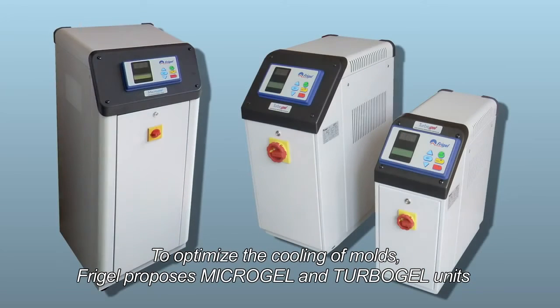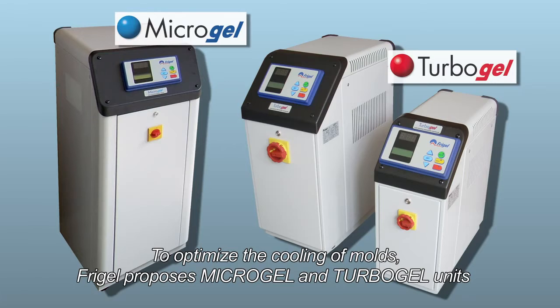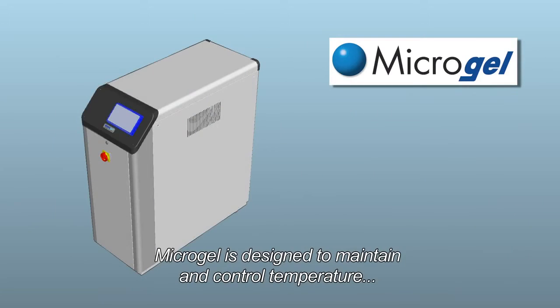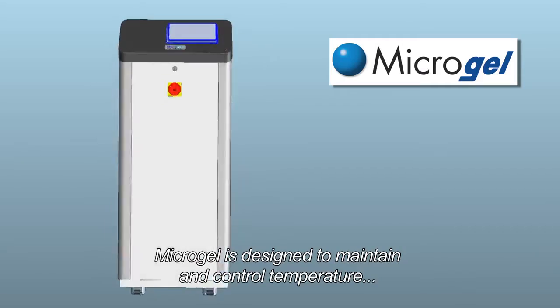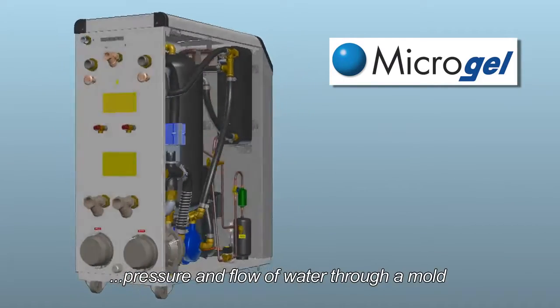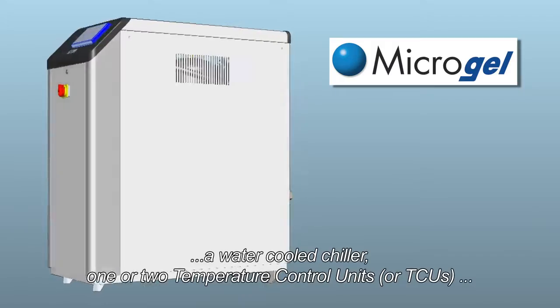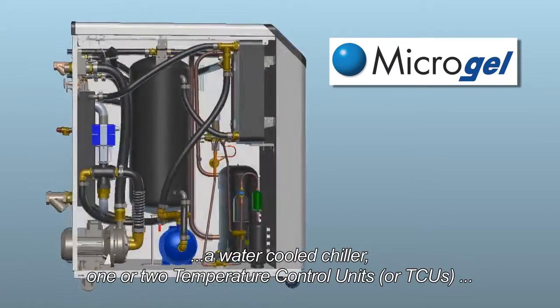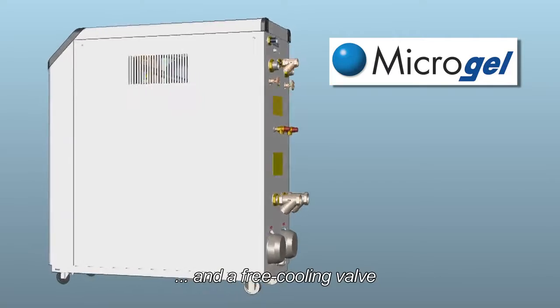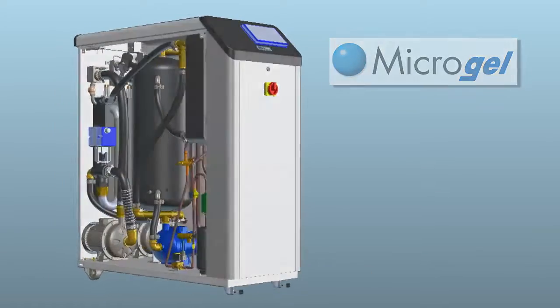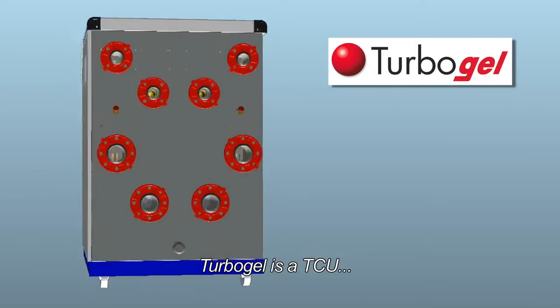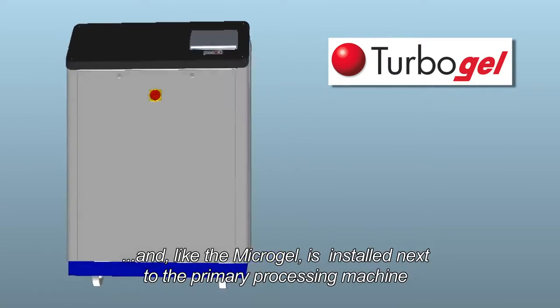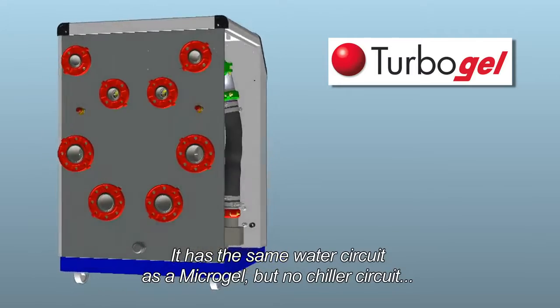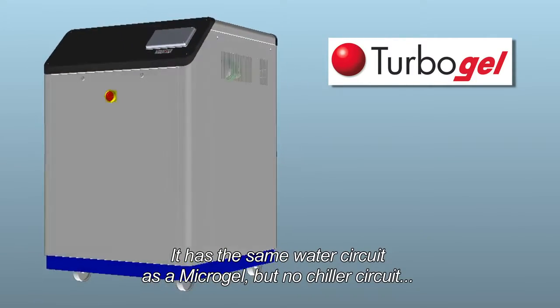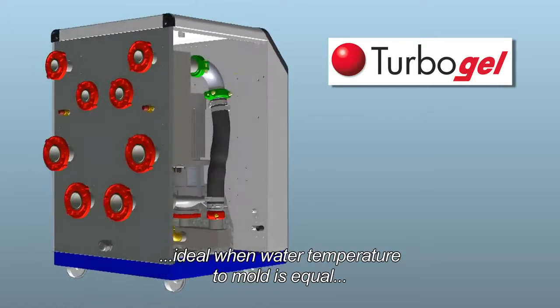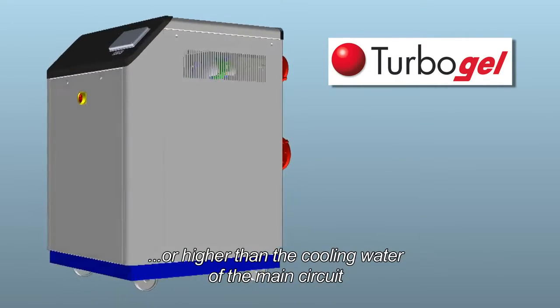To optimize the cooling of molds, Frigel proposes microgel and turbogel units. Microgel is designed to maintain and control temperature, pressure, and flow of water through a mold. It combines, in one machine, a water-cooled chiller, 1 or 2 temperature control units, or TCUs, and a free cooling valve, with a very compact size. Turbogel is a TCU, and like the microgel, is installed next to the primary processing machine. It has the same water circuit as microgel, but no chiller circuit. Ideal when water temperature to mold is equal or higher than the cooling water of the main circuit.